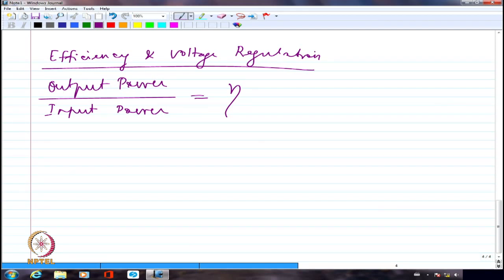That's the reason why generally the parameter estimation of a transformer becomes extremely important. That tells you indirectly, internally, how much the transformer is going to swallow and how much you will get at the output. So if I want so much power output from the transformer, how much should I be supplying? This is one thing. The second thing is, if I know that out of a 250 watt output of a transformer, maybe it is going to dissipate 20 watts, to that extent the transformer will get heated up.